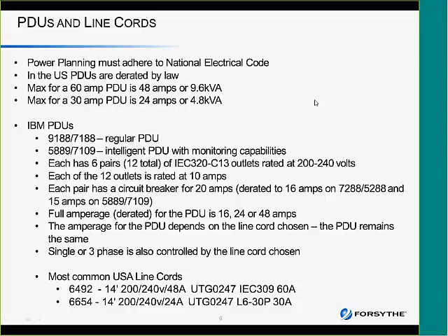If you attach a three-phase line cord with certain things, you can get 19.2 kVA. If you have a 60-amp line cord, then you get 9.6 kVA or 48 amps. So basically, if you have a 60-amp PDU, you are required to derate it to 48 amps. What that means is you can never commit to putting more than 48 amps or 9.6 kVA on that PDU. That's US law. And on top of that, the reason that they did it was because they had some fires because people overcommitted PDUs.